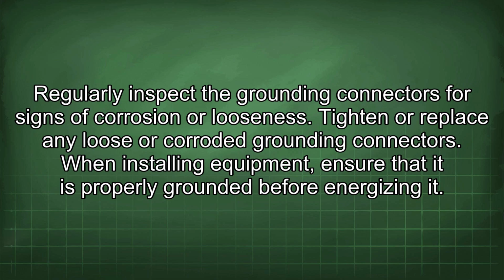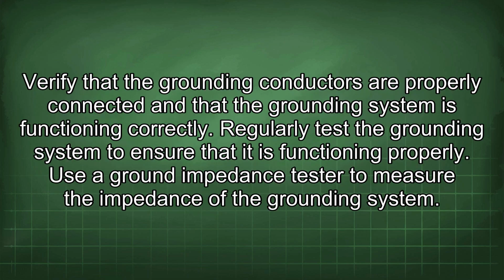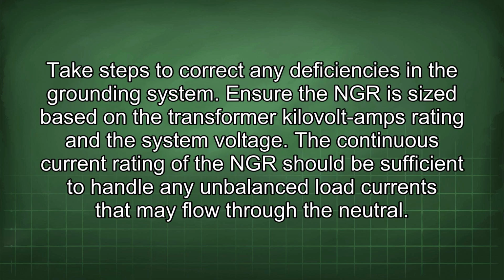When installing equipment, ensure that it is properly grounded before energizing it. Verify that the grounding conductors are properly connected and that the grounding system is functioning correctly. Regularly test the grounding system to ensure that it is functioning properly. Use a ground impedance tester to measure the impedance of the grounding system. Take steps to correct any deficiencies in the grounding system.